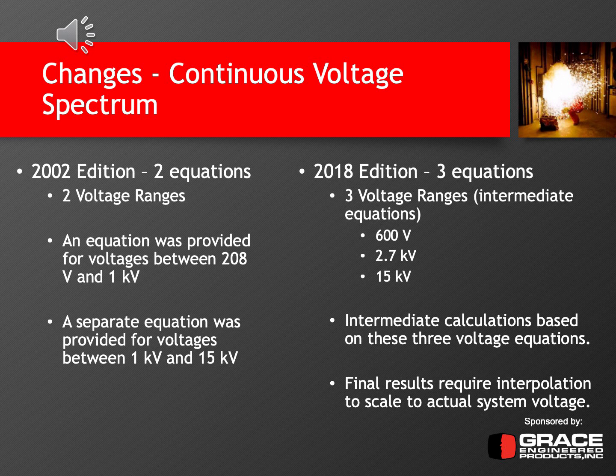As I stated earlier, the 2002 edition had basically two equations based on two voltage ranges. One was less than 1,000 volts, the other was between 1,000 volts and 15 kV. In 2018, there are three equations for three voltage ranges, the intermediate equations, and those ranges are 600 volts, 2.7 kV, and 15 kV.